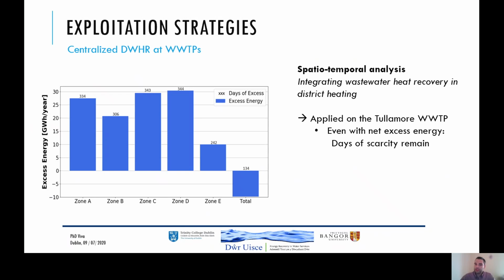Moving on to the temporal side of the analysis, then you can see here the net excess energy over a year for each of the 5 individual zones and for the combination of 5 zones. And you can see here for the 5 individual zones, the net excess energy is positive, meaning that the heat supply is larger than heat demand. But in all these cases, we still have a few days where heat supply is not sufficient to meet demand. On the other side, all zones combined has a negative net excess energy, meaning supply is smaller than demand, but we still have 134 days where supply was sufficient to meet demand.